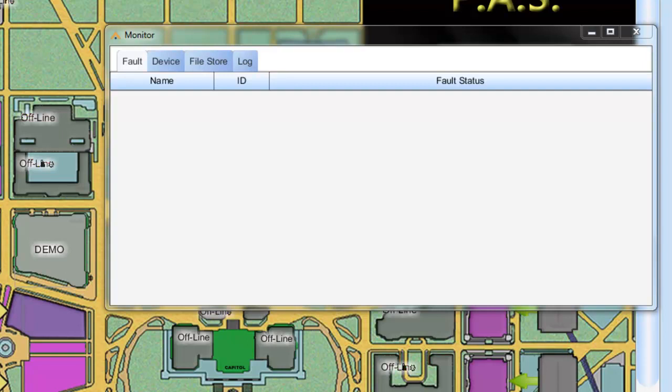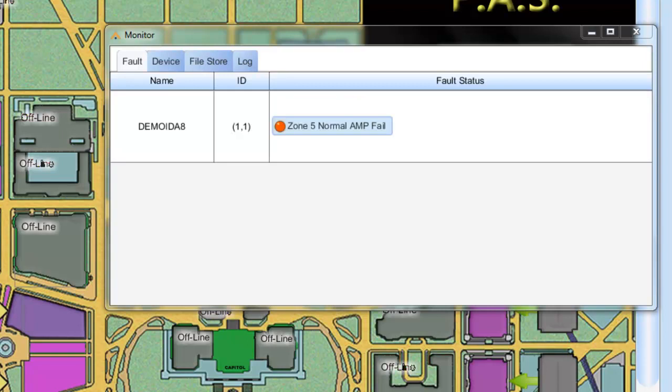And the first thing I'm going to do is disconnect the line level outputs that feed the amplifier input. They are disconnected now and it measures it two or three times to make sure it comes through. And you will hear the fault tone. There we go. And you can see on there it says zone 5 normal amp fail. And it actually says my demo IDA8 and it's unit number one on there. So it's telling me zone 5 of my unit. Now you can hear it beeping on the front panel. And actually on the front panel it says the exact same thing. Normal amp error for zone 5.